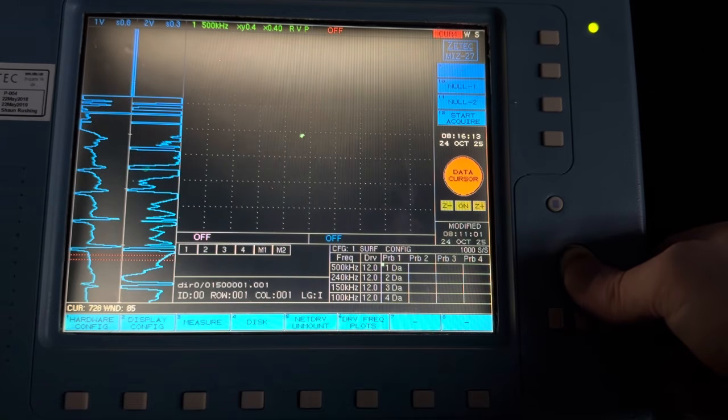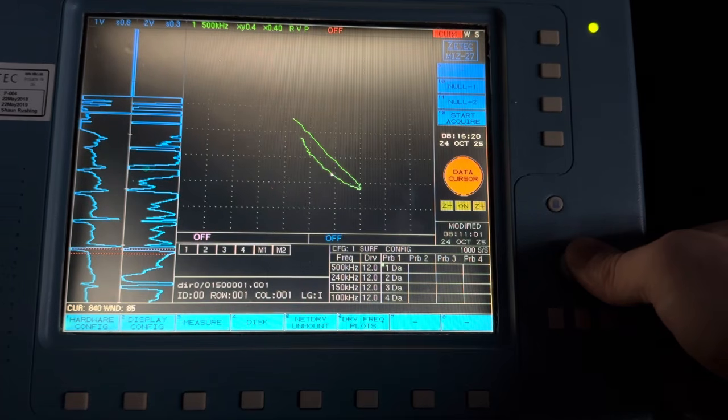What you want to do is start below the flaw, and then scroll up into that flaw. If it starts down and to the right first, that's going to be in the flaw plane for differential signals, as long as it's between 0 and 180 degrees. And that's only if you calibrate correctly using the right frequencies for the material you're testing and wall thickness.